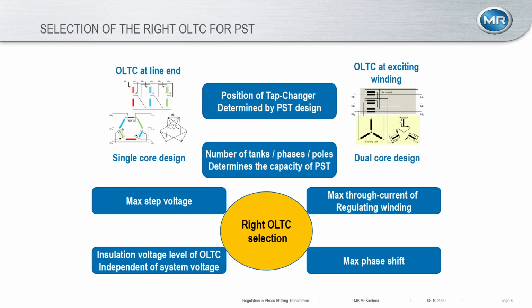If we look at the right selection of the OLTC, there are certain parameters that play a role. One thing is the PST design that determines the onload tap changer and especially its position. So if we look at the sketch on the left-hand side, you see a single core design. If we have a single core design, the onload tap changer is placed at the line end. So we have full voltage on the onload tap changer, and that would be a limit, of course, for the onload tap changer. We usually see that up to 245 kV. That would be a certain limit. Above that, this design is not possible anymore.